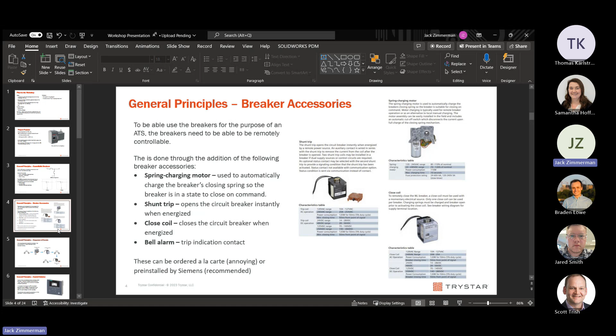And then, sequence of events: with the components installed in the breaker, they can complete a full open cycle remotely. This is basically a review - breaker's in an open state, let's say, and we want to close it and open it again. So the motor charger gets energized and charges up that coil. The closing coil then gets energized, closes the breaker, and then we energize the shunt trip right away to open it back up. So that shows full controllability over the breaker state through these couple of components.